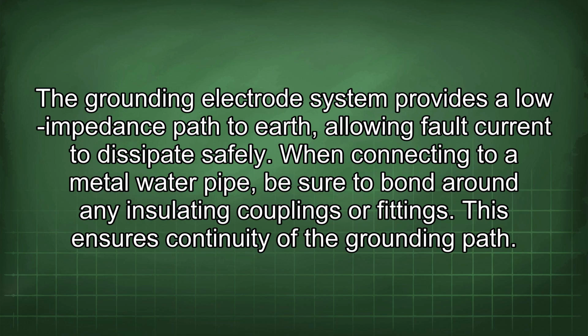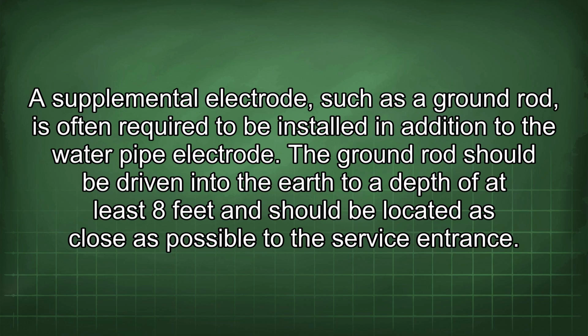When connecting to a metal water pipe, be sure to bond around any insulating couplings or fittings. This ensures continuity of the grounding path. A supplemental electrode, such as a ground rod, is often required to be installed in addition to the water pipe electrode. The ground rod should be driven into the earth to a depth of at least 8 feet and should be located as close as possible to the service entrance.